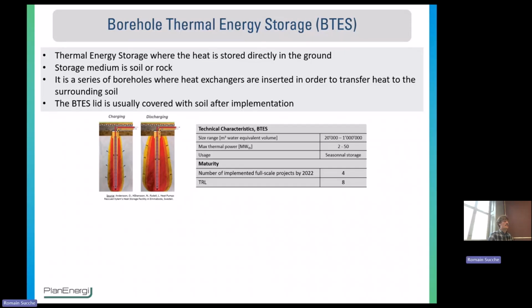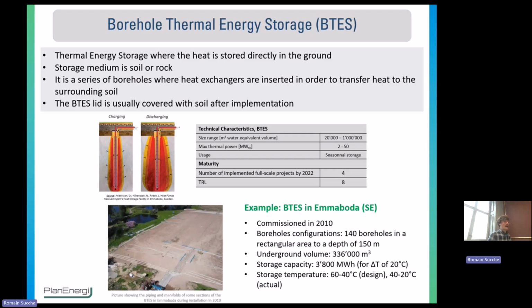The size range is a bit similar to pit thermal energy storage, from 20,000 to 1 million cubic meters equivalent volume. However, the thermal power is usually lower for boreholes, only from 2 to 50 megawatts thermal, and usually used for seasonal storage. And the example chosen was the one in Emmaboda in Sweden, commissioned in 2010. So 140 boreholes, and a storage capacity of almost 4,000 megawatt hours with a temperature of 20 degrees.